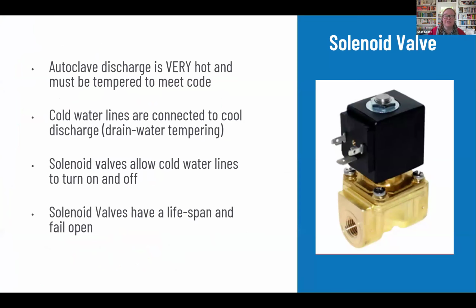Now, autoclaves discharge, and thank you, Robbie, for the setup, just to refer back to what he already shared with us, very hot water as part of their process. And plumbing code requires that water to be cooled to under 140 degrees Fahrenheit before it goes down the drain. Discharges hotter than 140 degrees can compromise the integrity of the drain lines and cause leaks or failures. It's very problematic.